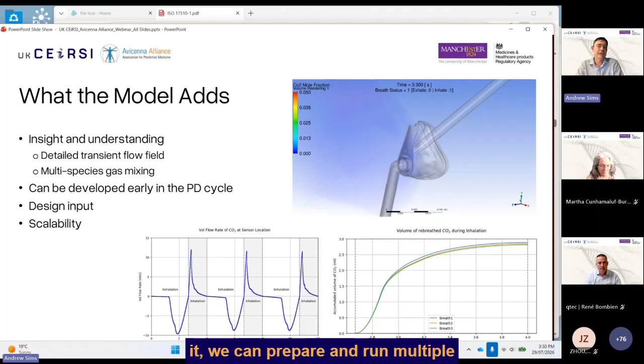Following on from what Martha presented, we had a specific question of interest. We followed the V&V 40 framework, and our question of interest is defined under ISO 17510 by the limits that we have there of not exceeding normal end-tidal CO2 without a mask by more than 20%. We're able to measure this from our model. Then we defined a context of use. In this case, we're proposing this to be a surrogate for bench testing, in which case our model influence becomes very high. But we do have bench testing available for validation.